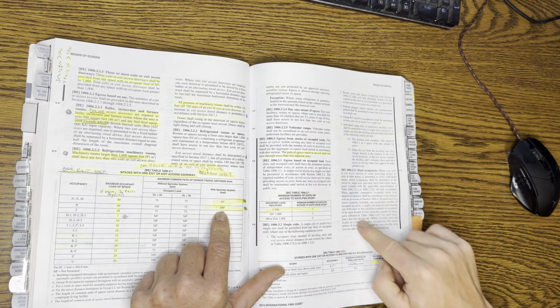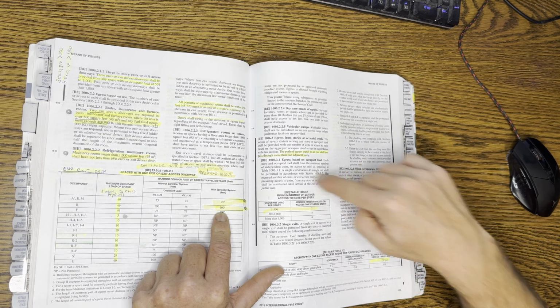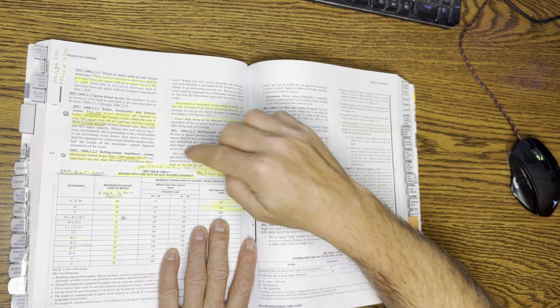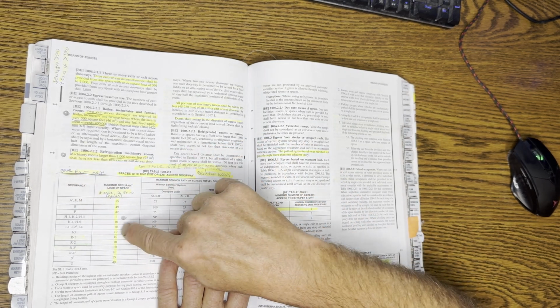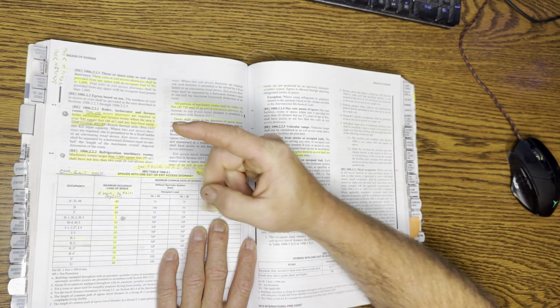So if I have a room that's like 100 feet wide, I know by default that I have to have 2 doors, period. And if I'm required to have 2 doors, it invokes other stuff, and I'll explain that. So that's how common path of travel works. This table is so you're allowed to have 49 people. It's a magic number for typical occupancies. There are some exceptions here, but let's not get caught up in those. So 49 people is a magic number for one door. If you have two doors, it invokes other things. You have to have emergency lighting. You have to have emergency exit signs, things like that.